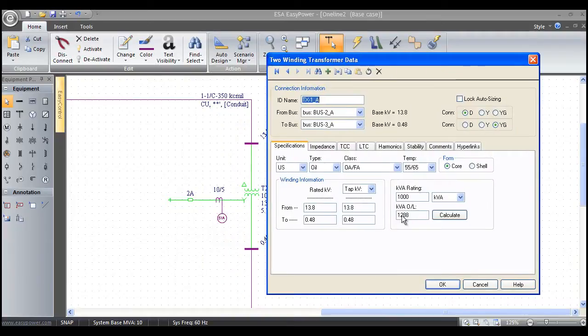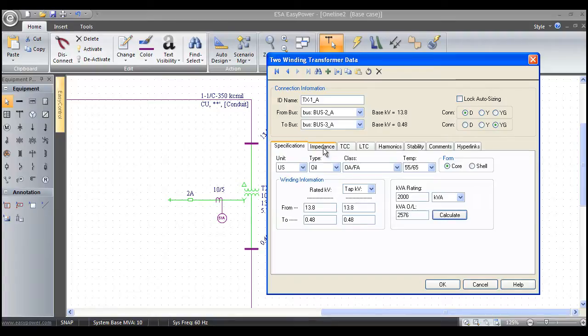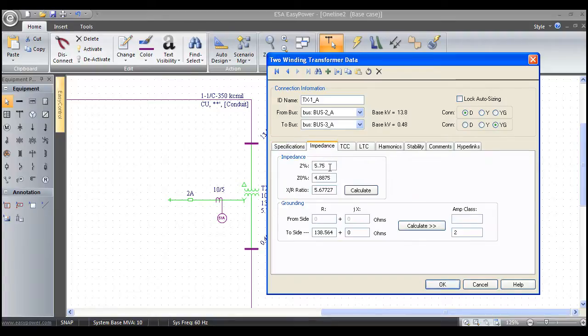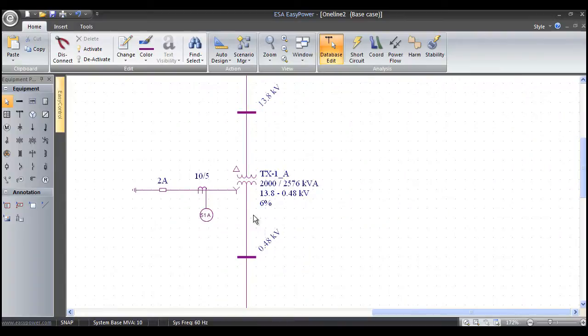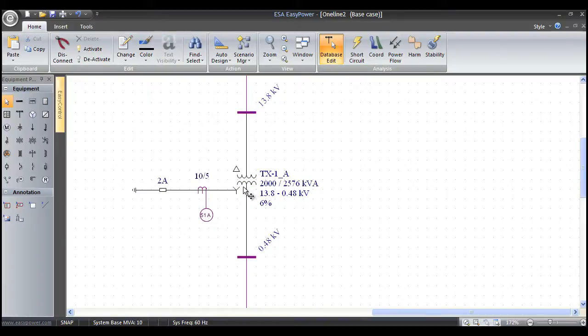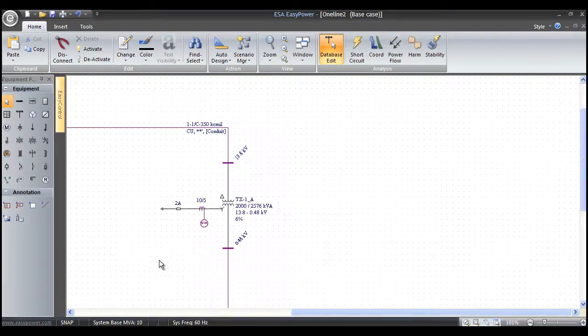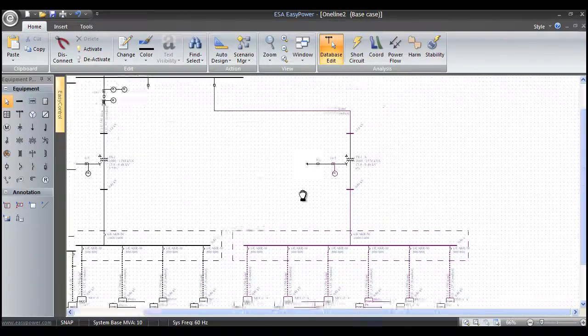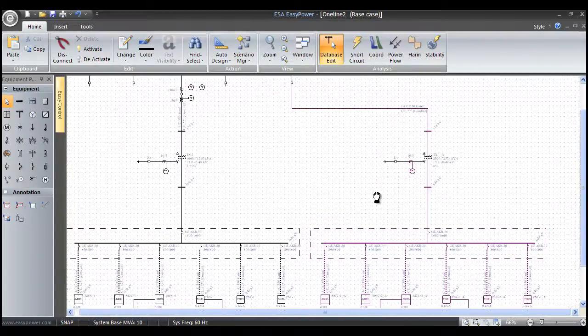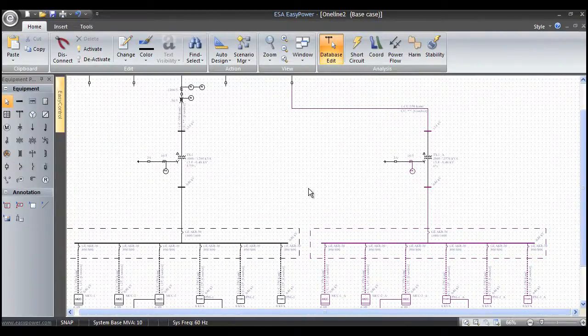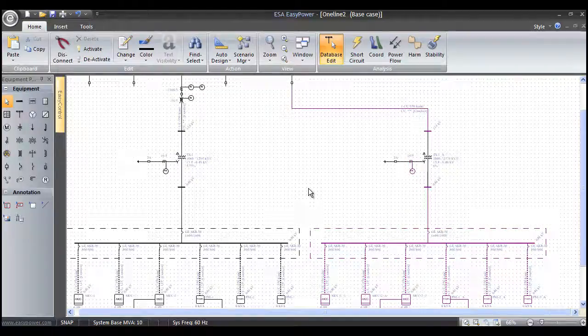I'll change that to maybe a 2,000 kVA. My impedance maybe changes to 6%. And once I do that, I'm okay. I highlight it. Come back to my color, change back to automatic. And that tells me that that data has all been updated. So it's very, very simple and easy to use as far as creating a one line.